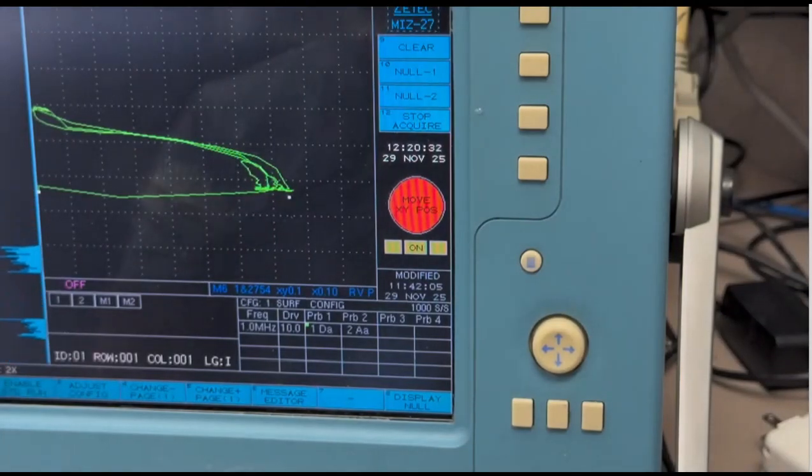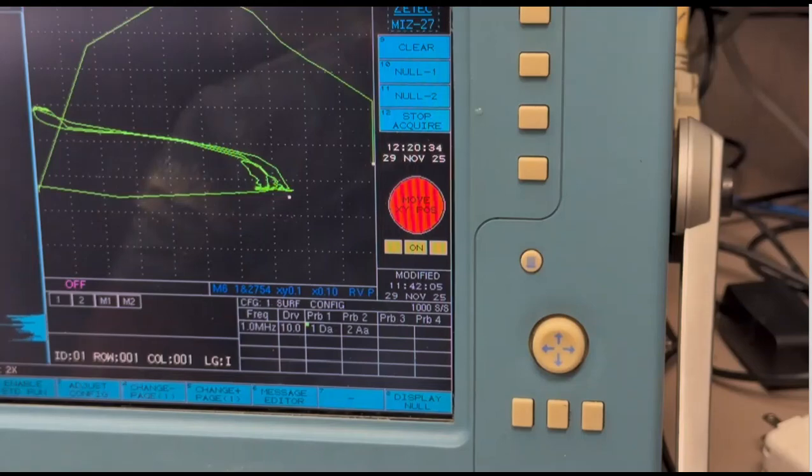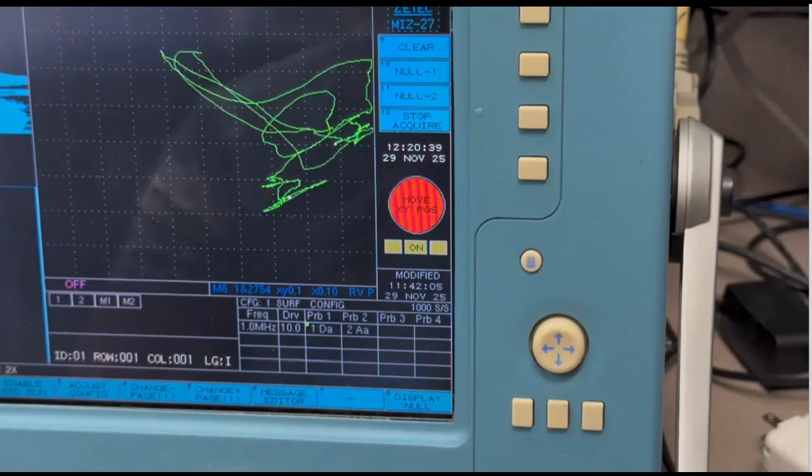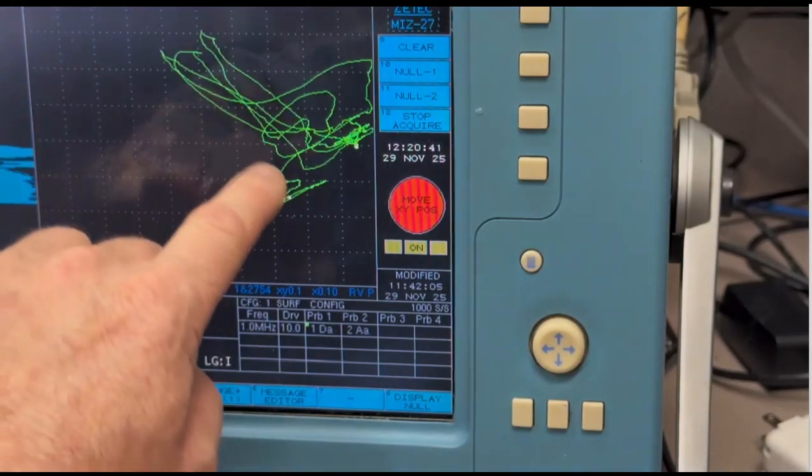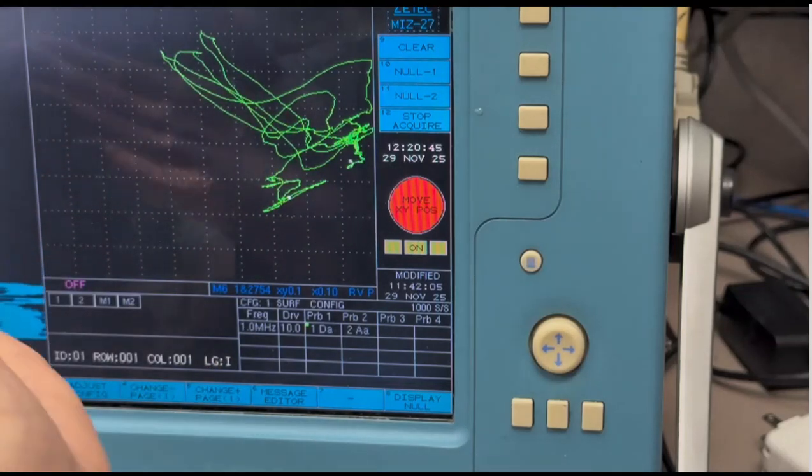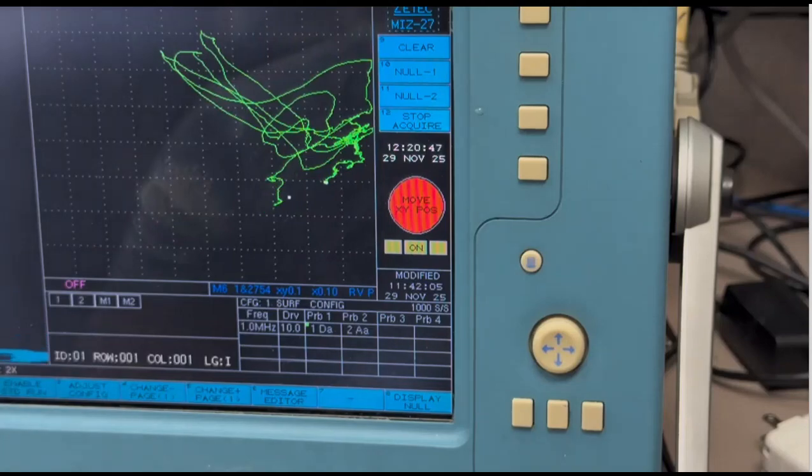So the next thing I'm going to do is take a sheet of Reynolds wrap and put it right on top of that EDM notch. I'm going to re-null and check out that signal. Not that beautiful, but now it's only about 40% of the screen height. But you can see that it tipped up clockwise because there's more phase lag.